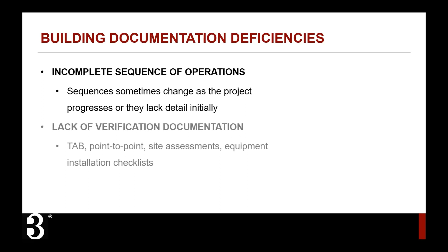Another issue is lack of verification of documentation. Some deliverables a commissioning agent normally performs include verification of test and balance on mechanical systems, point-to-point checkouts for controls on mechanical equipment, documentation of site assessments, who was met with, what was viewed, and equipment installation checklists. This documentation can be lacking, leaving the owner with no reference on whether things were checked out, whether the test and balance was verified, or the TAB report reviewed.